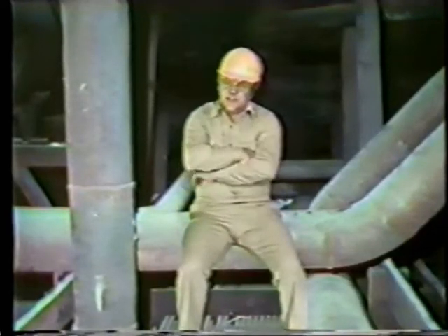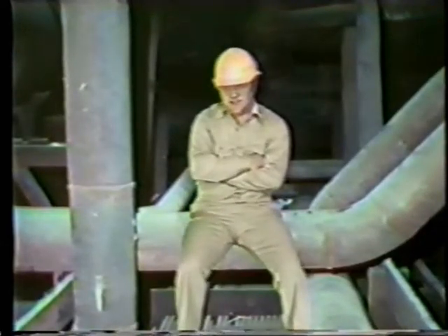The major difference is this partition. It divides each water box into an inlet section with the first-pass tubes, and, unlike a single-pass condenser, an outlet section with the second-pass tubes. This design causes the circulating water to flow through the condenser twice, or in other words, make two passes through the condenser. The operation of a single-pass and two-pass condenser is very similar on the steam side.